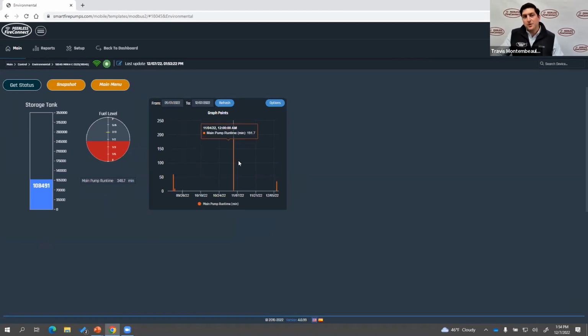And if you have to care about emissions reporting, so if you're in California, for example, we give you the daily runtime as well, based on how long you run that fire pump for. So 35 minutes it's run today, for example. You can then use that to fill out the forms that you're required to do per state requirements in California. So we're trying to simplify from an emission standpoint some of the reporting that also has to happen here.